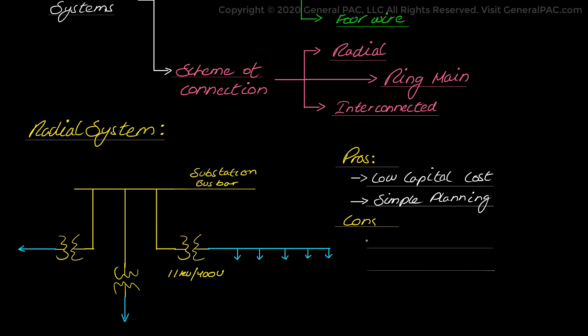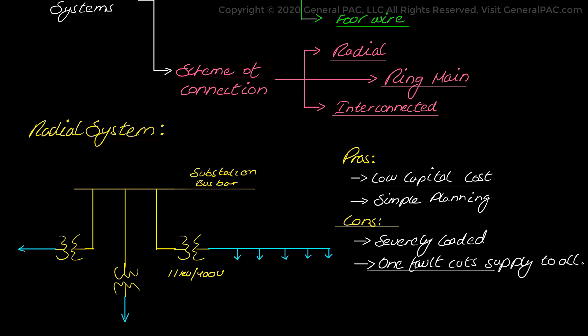However, radial systems also have drawbacks. The portion of the distributor near the feeding point will be severely loaded. The consumers are dependent on a single feeder, so any fault on the feeder or distributors cuts off supply to consumers who are on the other side of the fault, away from the substation. Consumers at the far end of the distributor are subject to voltage fluctuations when the load changes. Due to these limitations, it is preferred to use this system only for short distances.